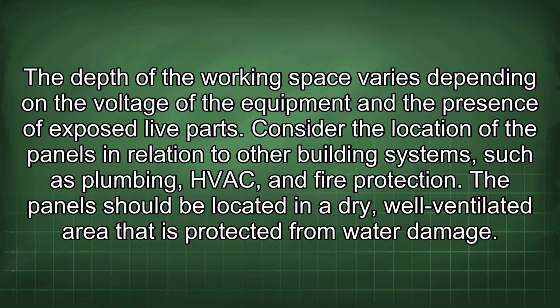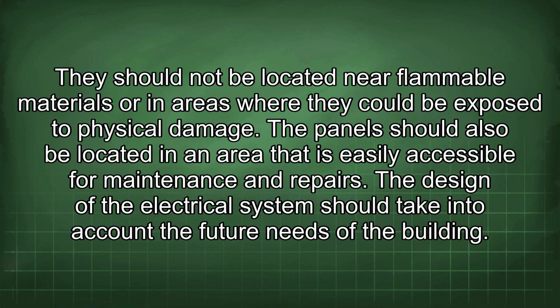The depth of the working space varies depending on the voltage of the equipment and the presence of exposed live parts. Consider the location of the panels in relation to other building systems such as plumbing, HVAC, and fire protection. The panels should be located in a dry, well-ventilated area that is protected from water damage. They should not be located near flammable materials or in areas where they could be exposed to physical damage. The panel should also be located in an area that is easily accessible for maintenance and repairs.